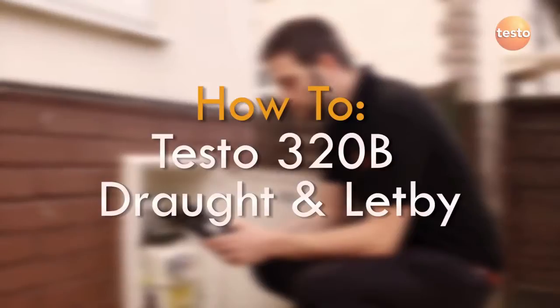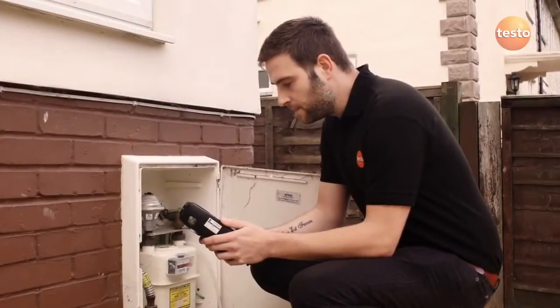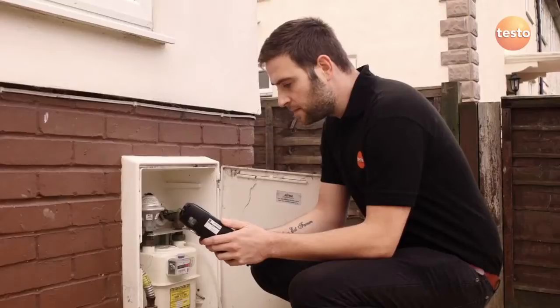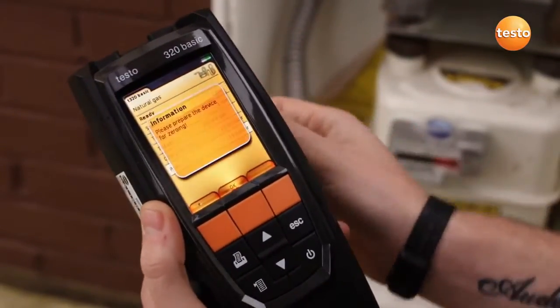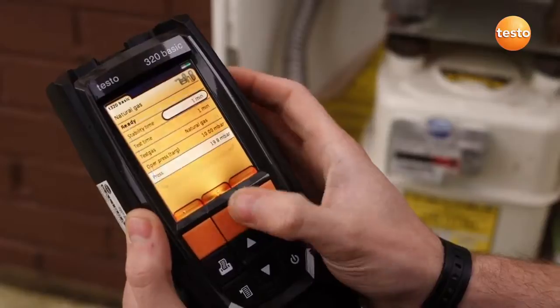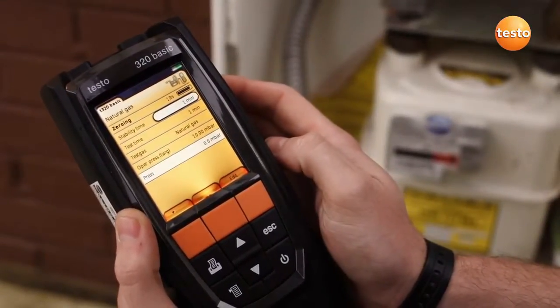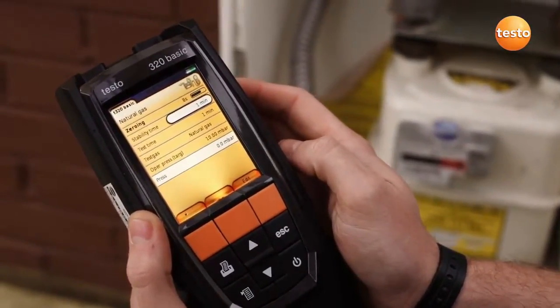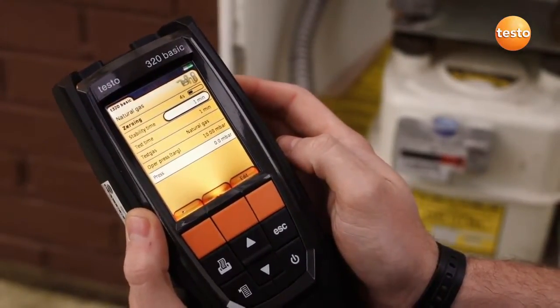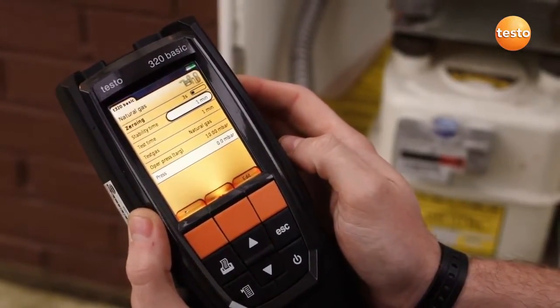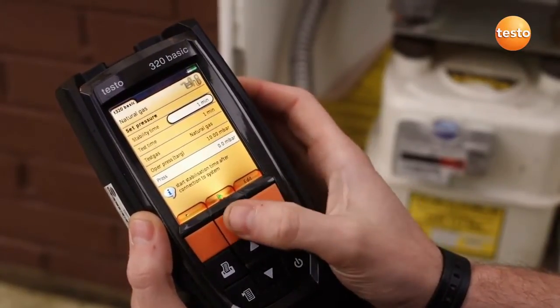The 320B includes a menu for carrying out let-by and tightness tests on pipework. Access the let-by and tightness tests from the main measurement menu. Make sure the analyzer isn't connected to anything to allow the pressure sensor to be zeroed. The let-by test is displayed with default settings. The stability time, test time, and target pressure can all be edited according to the let-by standard you are working to.